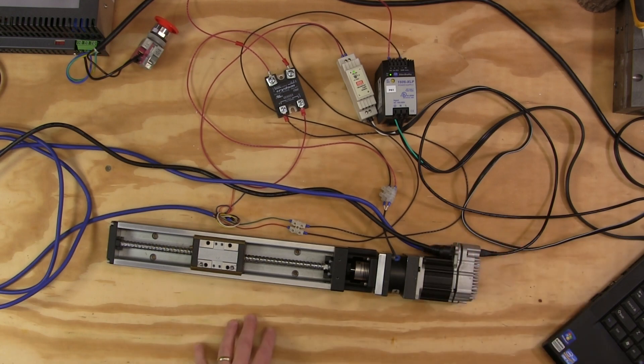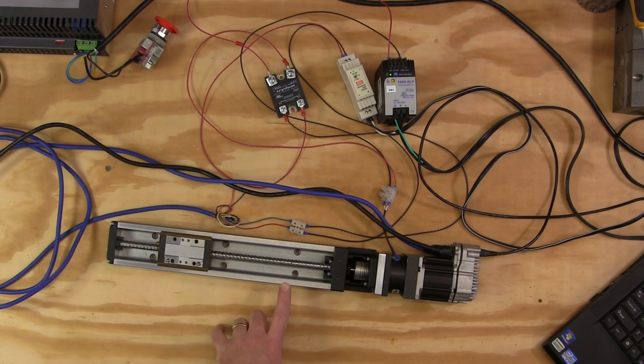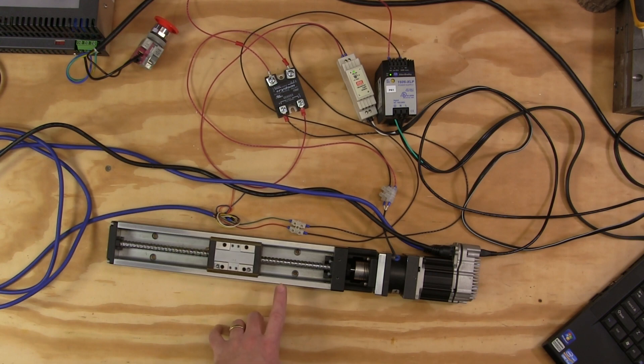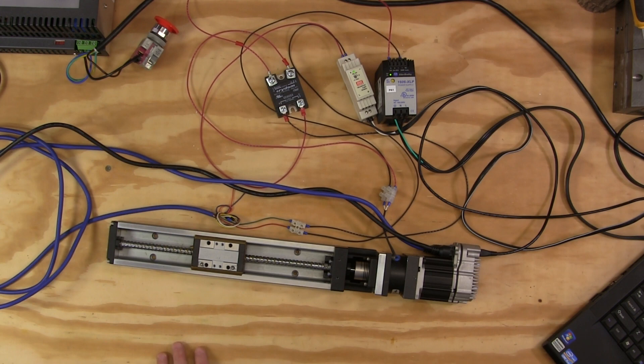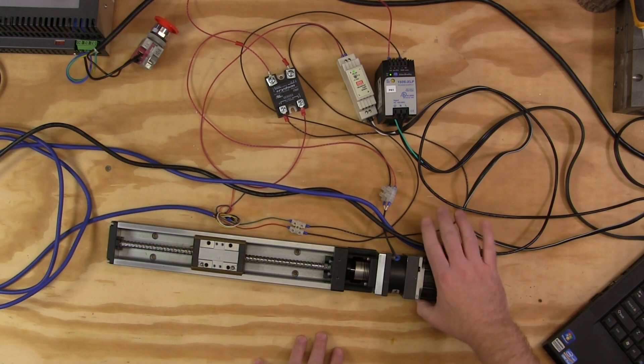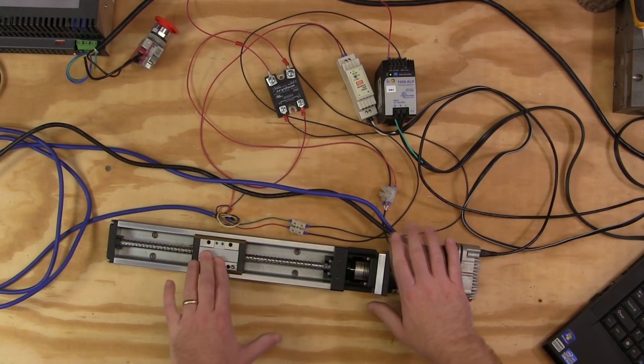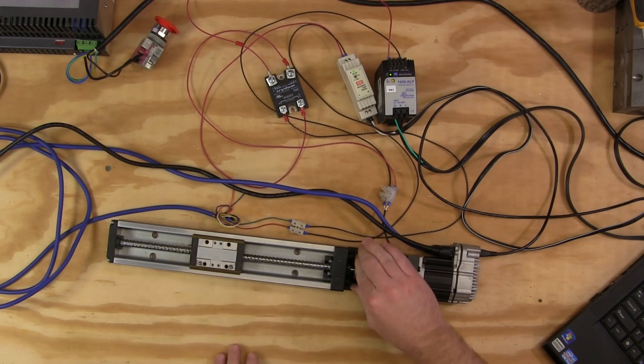I can go through the software and I can actually jog the motor and it jogs with no issue. And this is just inside the diagnostic program so this is not like a speed move that you would have on a CNC machine. So if I go back and disable the motor, the motor goes disabled so it's not holding the load anymore. The brake steps in and prevents rotation and we can no longer move the shaft.